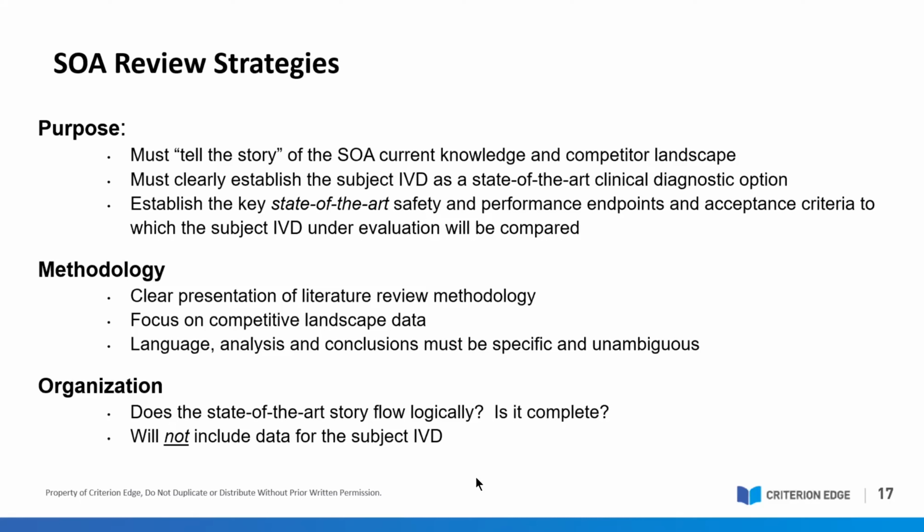The IVDR puts a lot of emphasis on the clinical relevance of the diagnostic device. So in addition to the generally acknowledged state of the art of the devices and the performance of a device, particularly the clinical evidence and the clinical benefit, all of those need to take into account the state of the art in medicine with regard to this particular clinical field, this particular clinical scenario. Within another section of the IVDR, Article 56, they state that the clinical evidence shall be such as to scientifically demonstrate, by reference to the state of the art in medicine, that the intended clinical benefit will be achieved and that the device is safe. So again, it's referring you back to the state of the art in medicine.